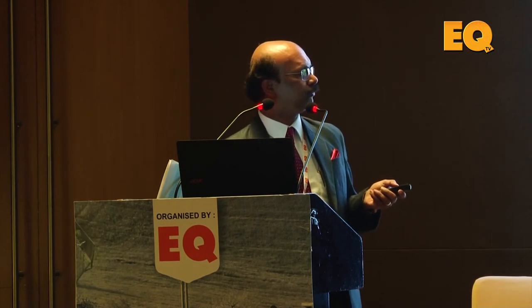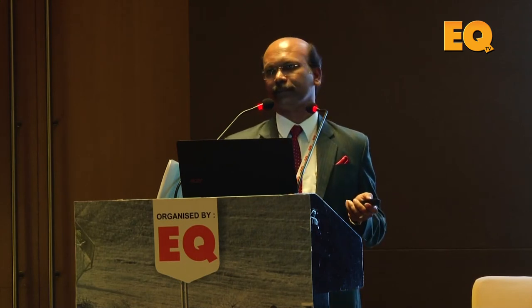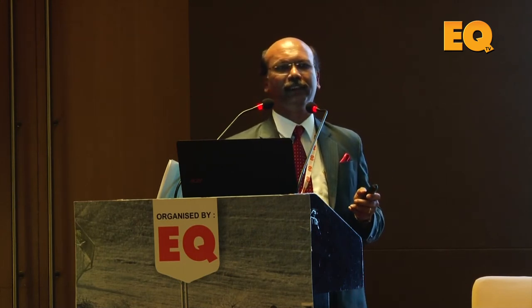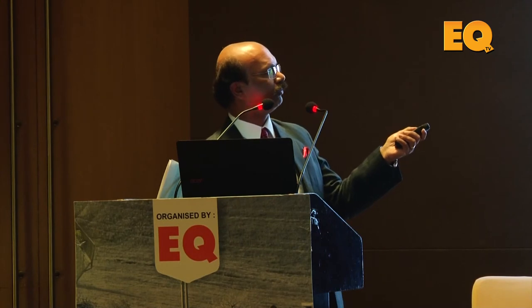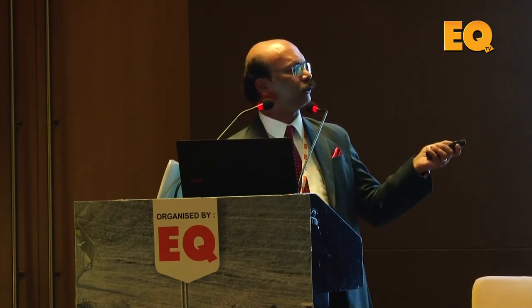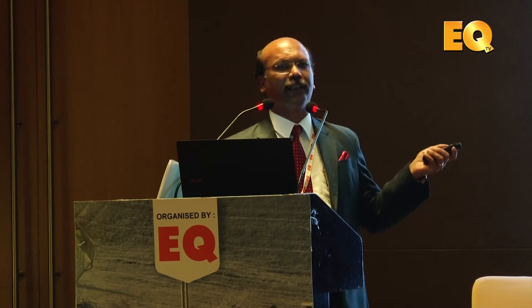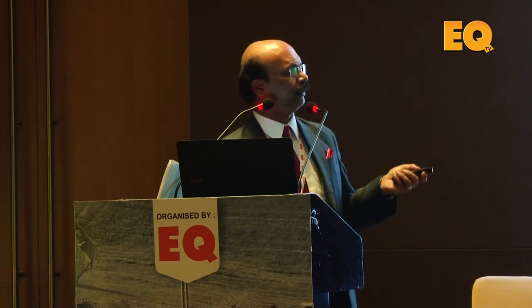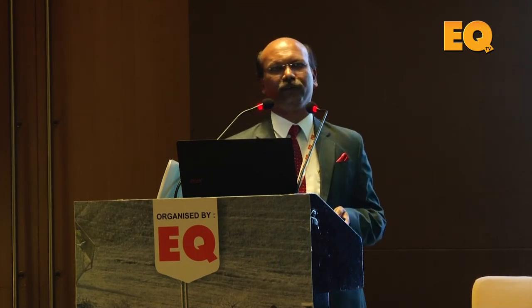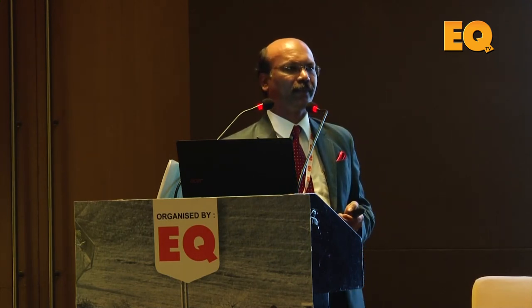So in absence of solar, in absence of SolGrid, let's see what happens. As we know, as soon as the grid is off, we need a reference for the solar power to work, so the diesel generator has to be on. But when we turn on the diesel generator, in absence of this kind of controller, it is very difficult to know at what level we should maintain it. Therefore, the diesel generator might be working on its own without maintaining an optimum level, and there could be high diesel consumption.